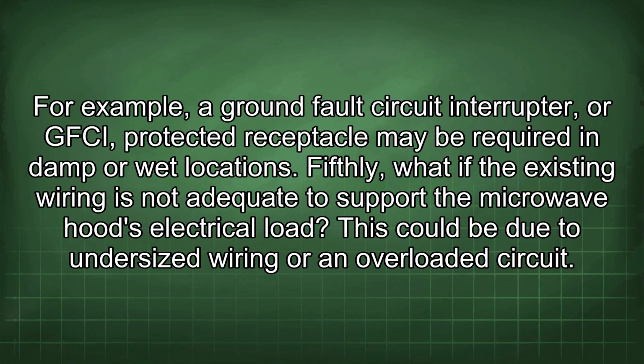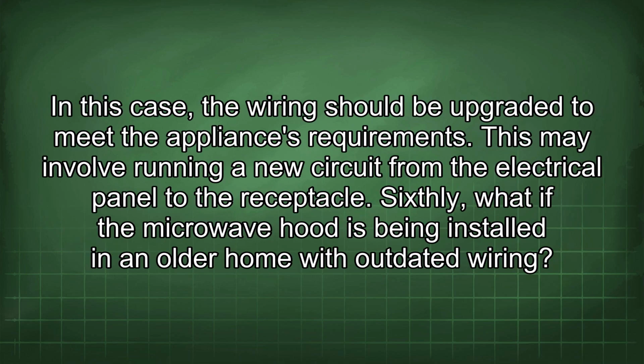Fifthly, what if the existing wiring is not adequate to support the microwave hood's electrical load? This could be due to undersized wiring or an overloaded circuit. In this case, the wiring should be upgraded to meet the appliance's requirements. This may involve running a new circuit from the electrical panel to the receptacle.